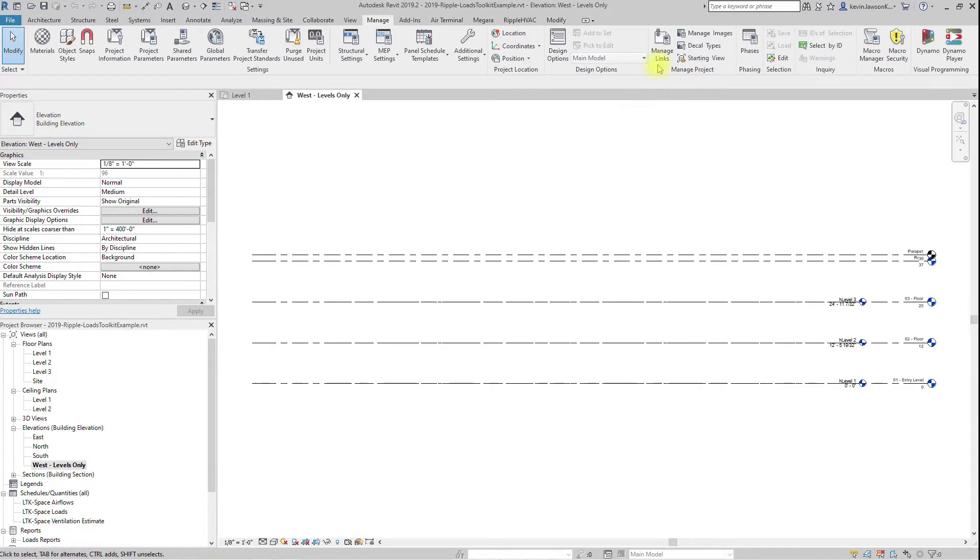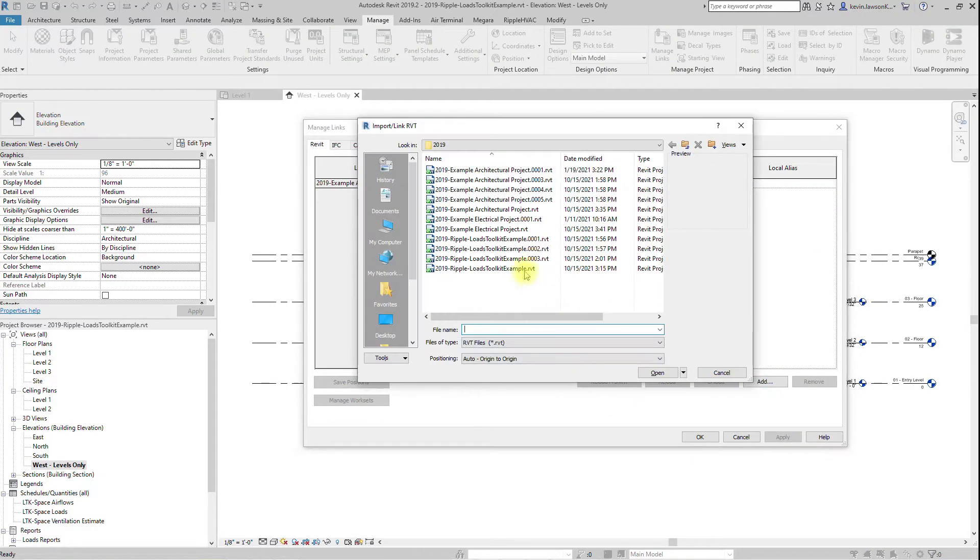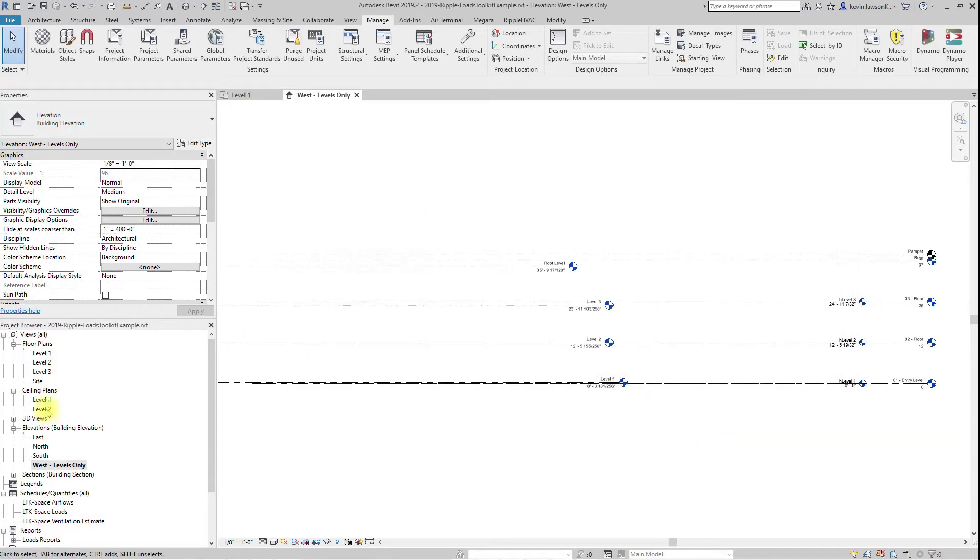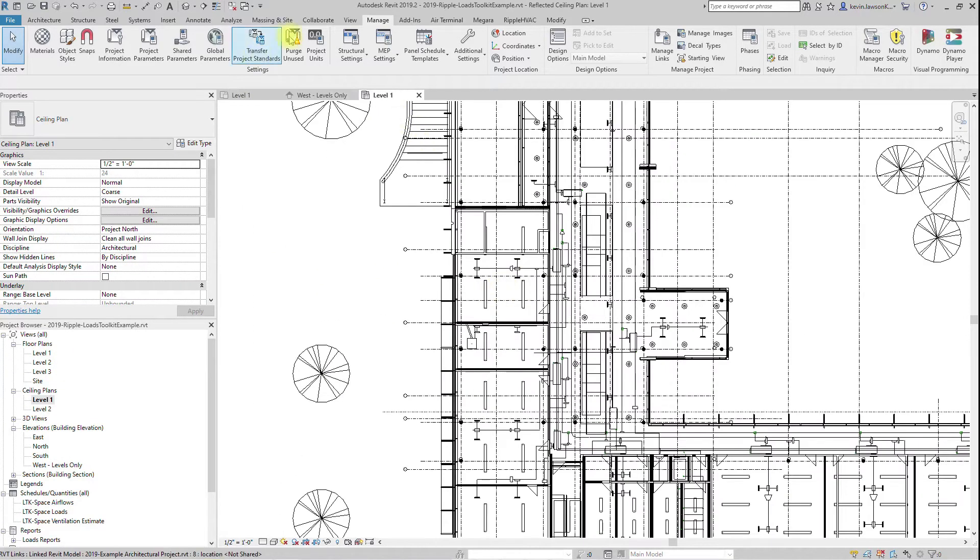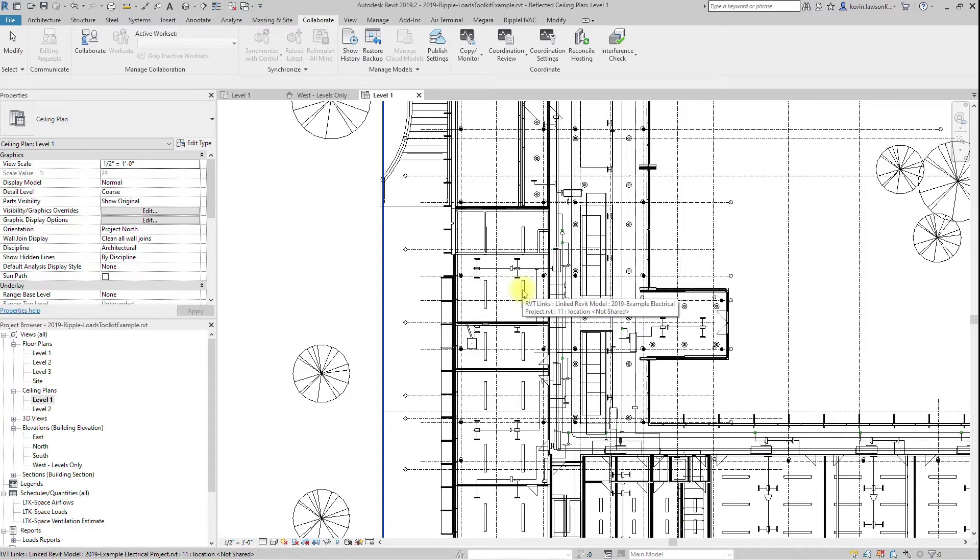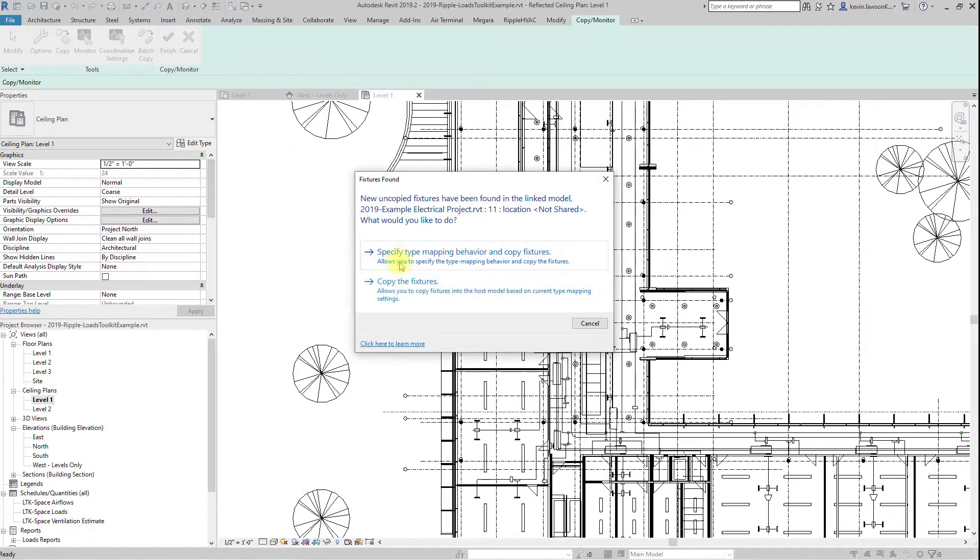If your firm uses separate mechanical and electrical models, and you would like to use the actual electrical data for loads, you will need to link in the electrical model and copy monitor in the light fixtures and the electrical fixtures category. This will allow you to pull the electrical data from the actual electrical elements into your space load.